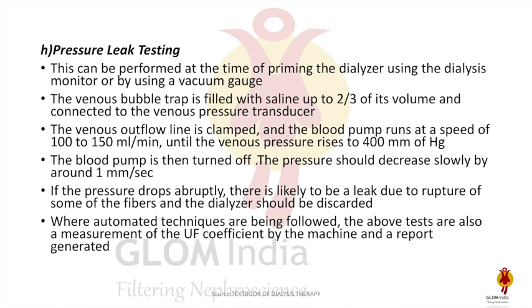For pressure leak testing manually: the venous bubble trap is filled with saline up to two-thirds of its volume and connected to the venous pressure transducer. The venous outlet line is clamped and the blood pump runs at 100 to 150 ml per minute until venous pressure rises to 400 mmHg. The blood pump is then turned off and the pressure should decrease slowly at around 1 mmHg per second. If the pressure drops abruptly, there is likely a leak due to rupture of some fibers and the dialyzer should be discarded.